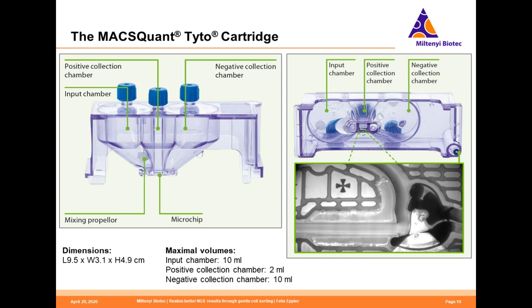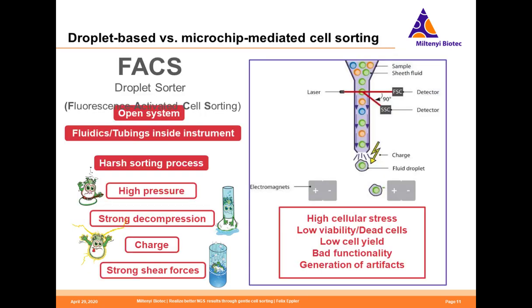Now that you have seen this animation and also the video of the micro valve — an opening and closing cycle only takes around 30 microseconds, so the micro valve can move up to 30,000 times per second — it becomes quite obvious that this is a very different cell sorting technology compared to the classical FACS, the fluorescence-activated cell sorting droplet sorter.